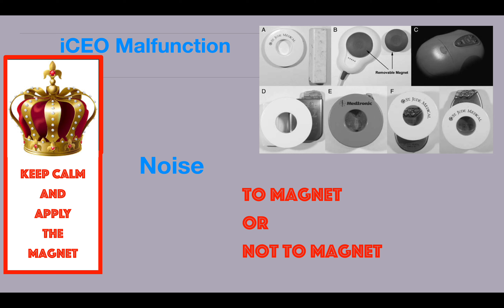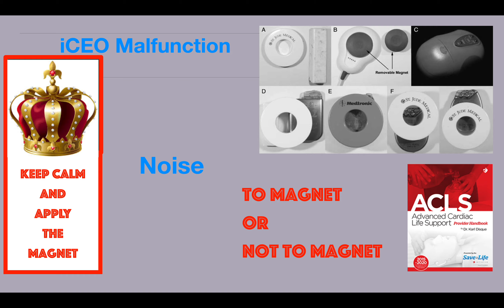To magnet or not to magnet? The everlasting question whenever an iCEO makes its debut in the operating room. Magnets come in 40 shades of colors and shapes. When the magnet is correctly placed over the device, beeping tones appear 1 second later and for 1 long minute. When was it you last used such a magnet? One might wonder when magnets will find their way to the Advanced Cardiac Life Support course in order to familiarize people with that. In a noisy operating room, we magnet to increase the fidelity of the iCEO and stop it responding to any seductive noise.